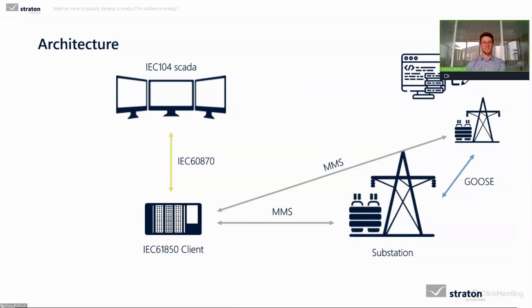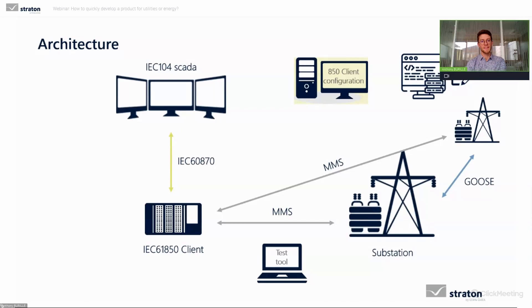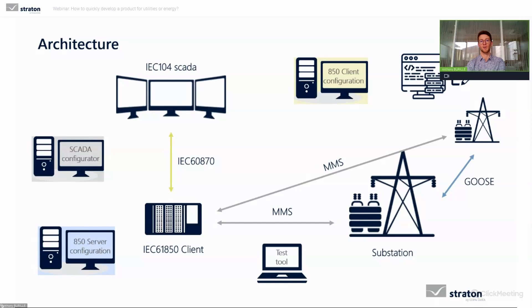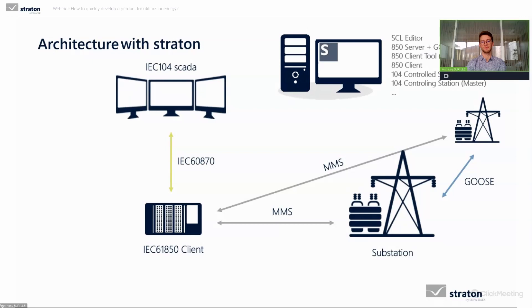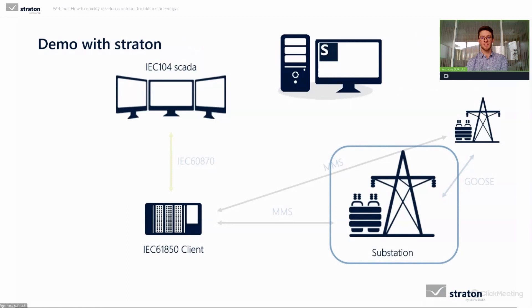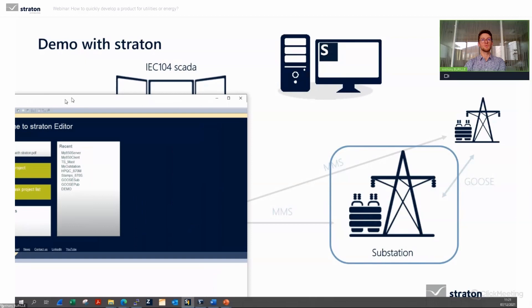Everything can come from independent manufacturers — which is completely fine, because as Pascal said, if everything is compliant with the standard everything can communicate easily, keeping interoperability between every element. The first point is creation of the SCL file — our 61850 server configuration file — we will configure it to simulate a circuit breaker, send its values to a client through MMS, and communicate its internal status to other servers with GOOSE. We will need only one editor with everything included.